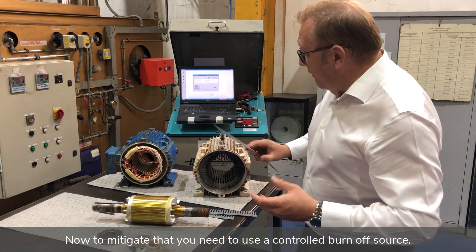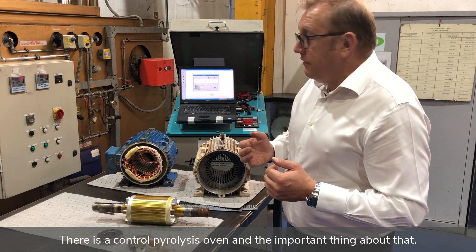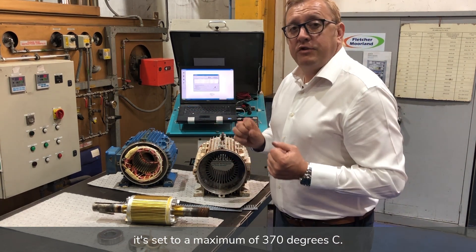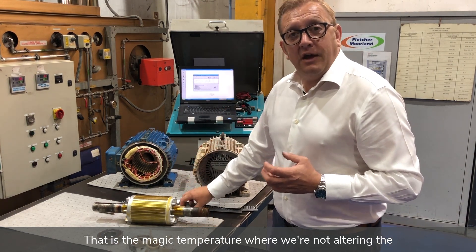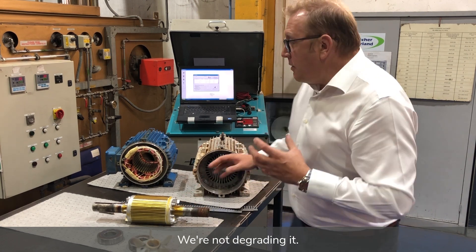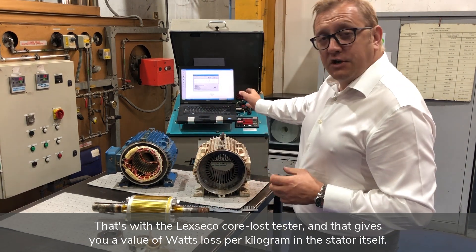To mitigate that, you need to use a controlled burn-off source — a controlled pyrolysis oven. The important thing about that is it's set to a maximum of 370 degrees C. That is the critical temperature at which we're not altering or degrading the insulated coating layer. To prove that, a core loss test is carried out using the Lexseco core-loss tester.